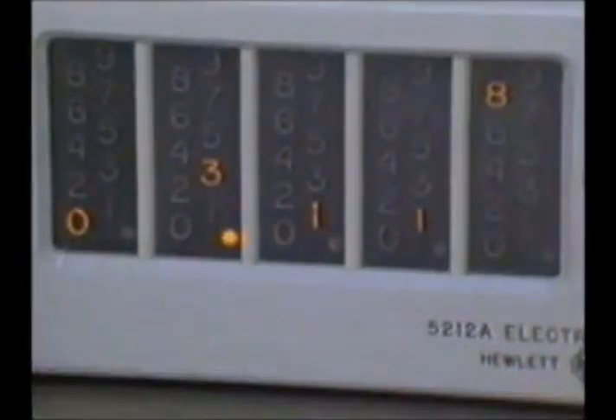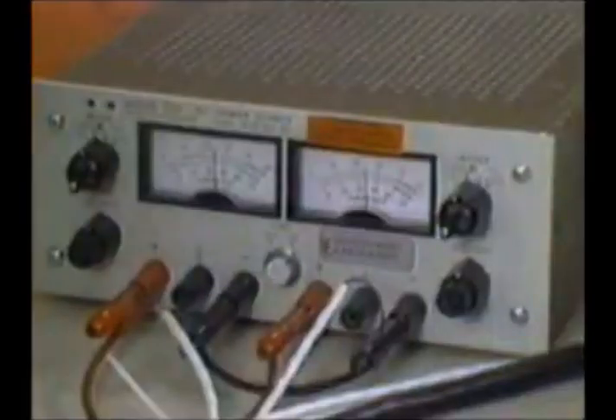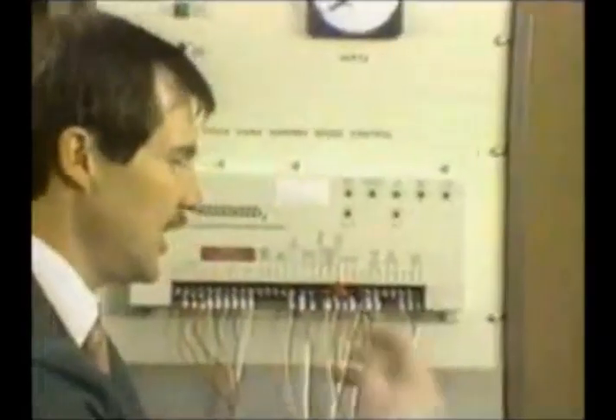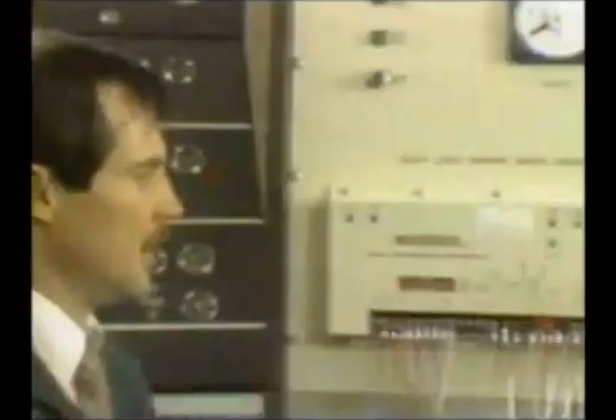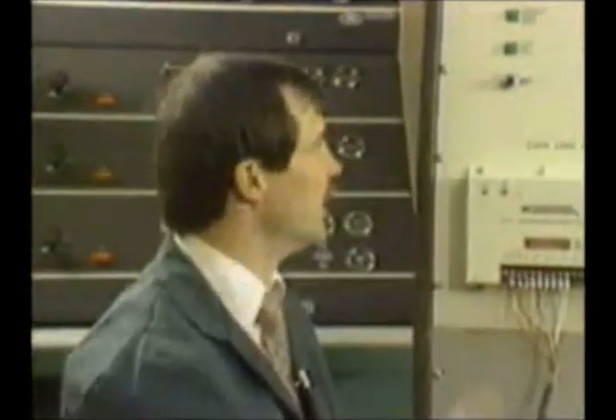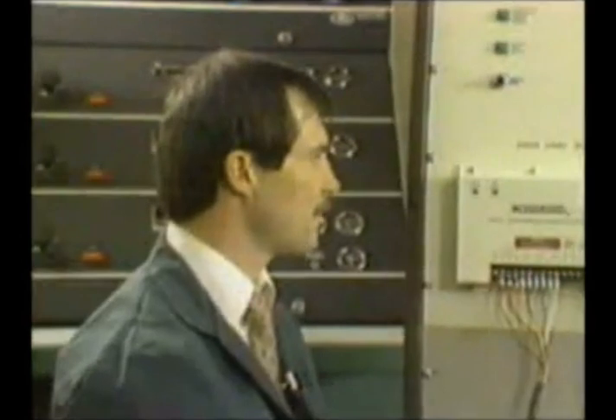We're going to start up in idle. We're going to start up around 3119. My power supply is turned on. So now as I hit the start button, we're going to come up to idle speed. Engine starts up. We're running at idle speed. Should be around 1200 RPM. Doesn't show up on the Hertz meter. We're not high enough to be on the Hertz meter.